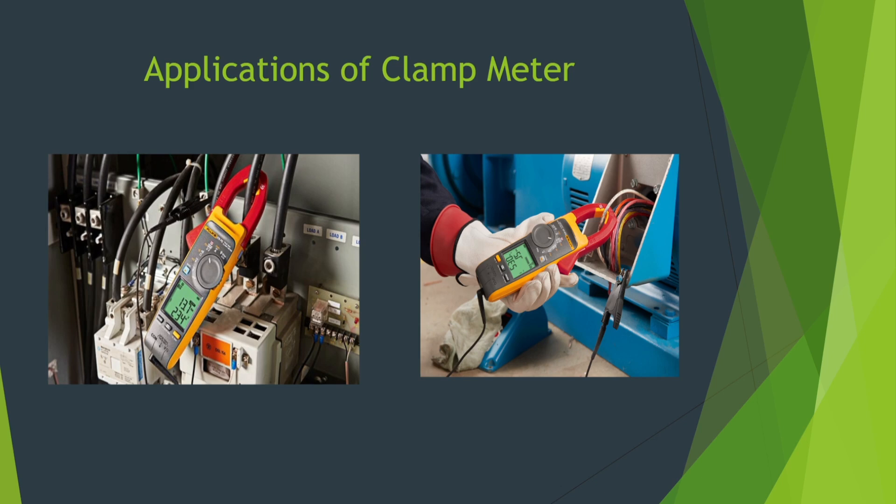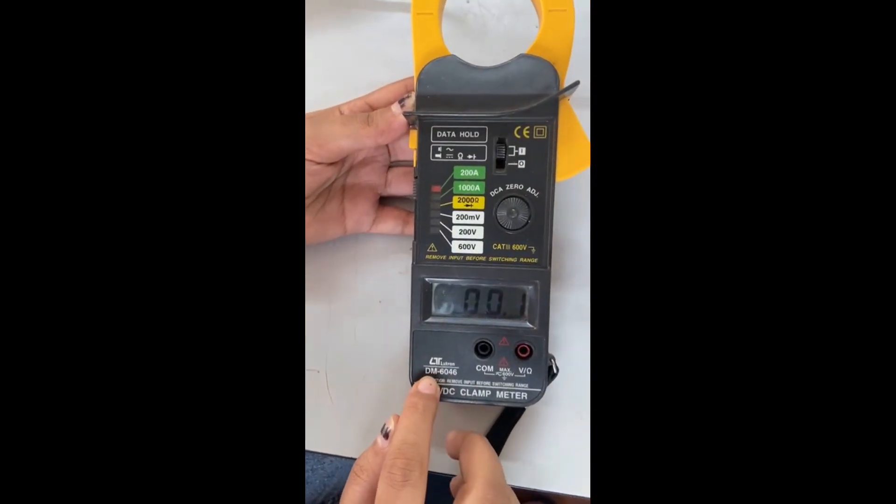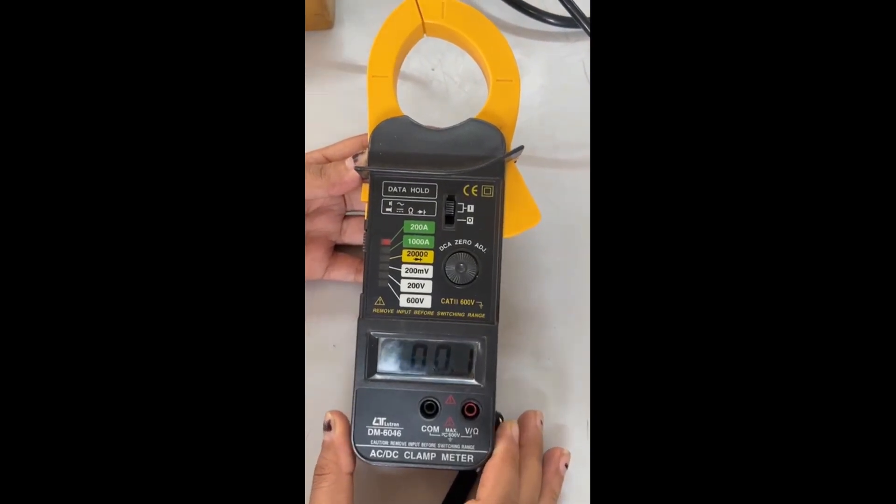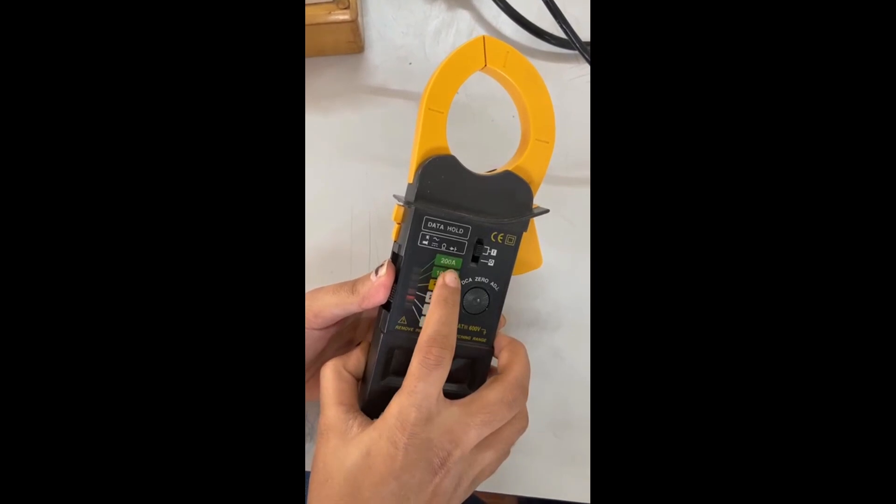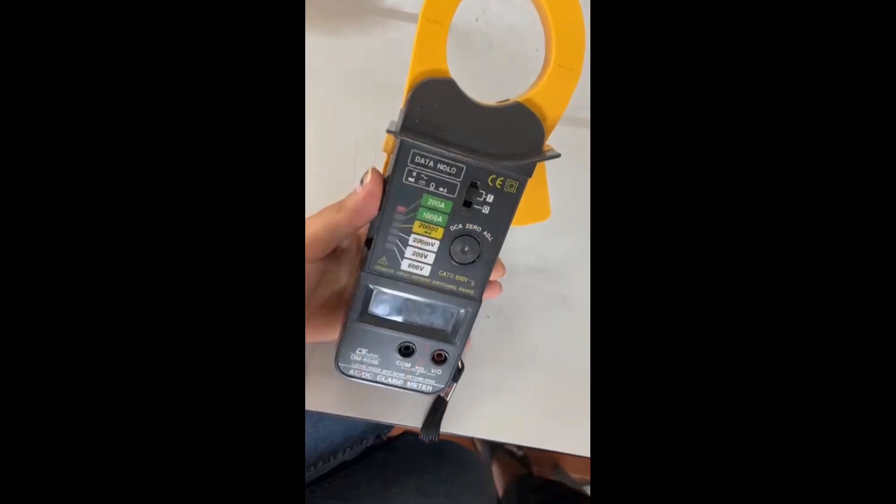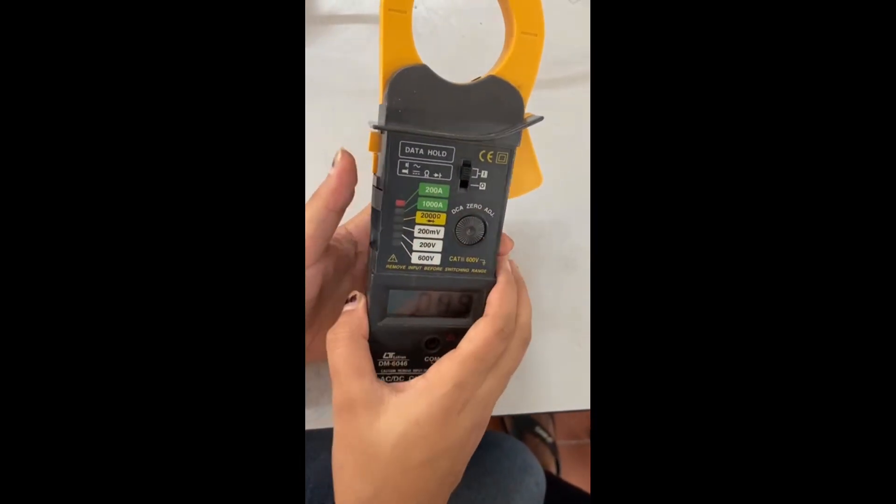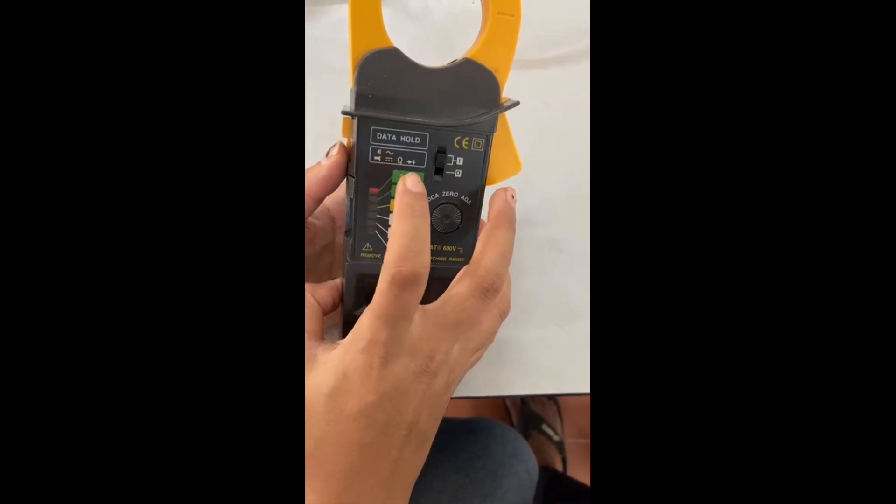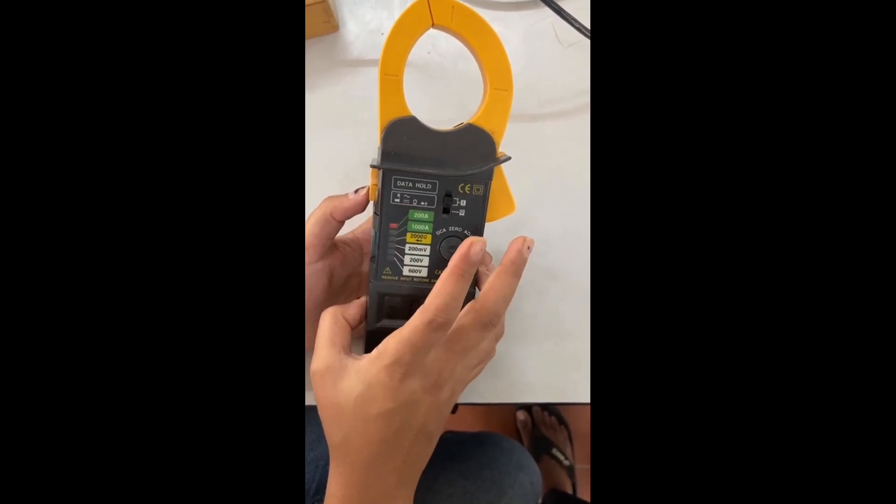Let's see a demonstration video of how to use clamp meter of brand Lutron whose model number is DM6046. We are going to demonstrate how to measure various parameters that are given on the meter. Let's start with current. So to set it on current we will use this slider to set it on different limits. We will set it on 200 amperes for our setup. This yellow button here is used to change the mode of the clamp meter. There is AC mode and there is DC mode, diode mode. So we will press it like this to set it on AC.